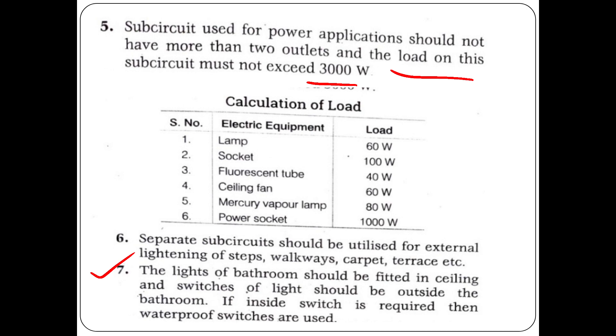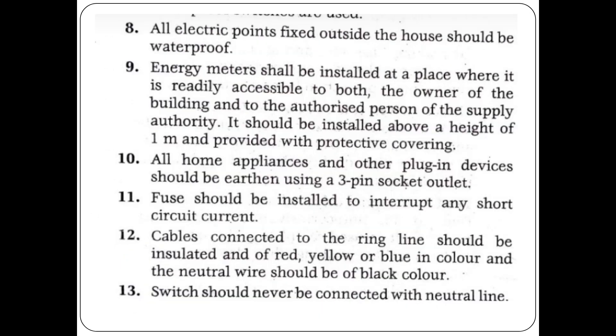Seventh point: the lights of a bathroom should be fitted in the ceiling, and the switches of those lights should be outside the bathroom. If a switch is inside, it should be waterproof. All electric points fixed outside the house should be waterproof.